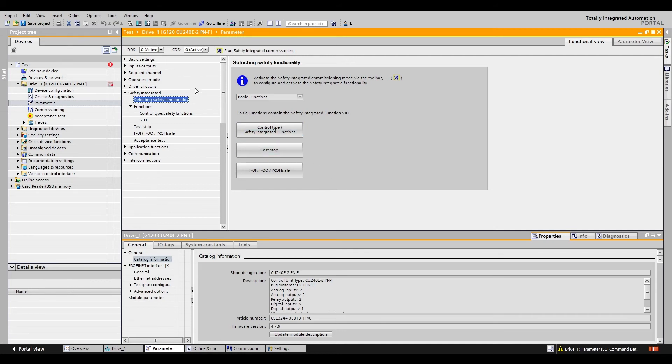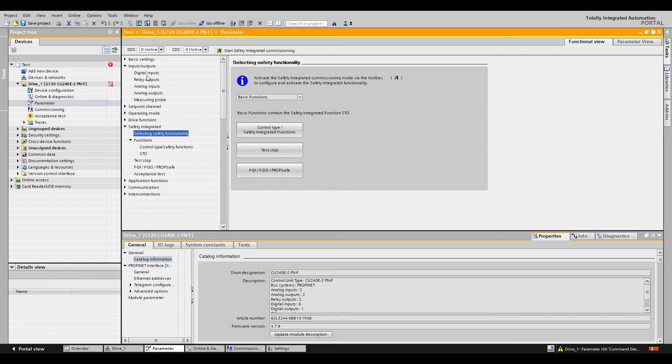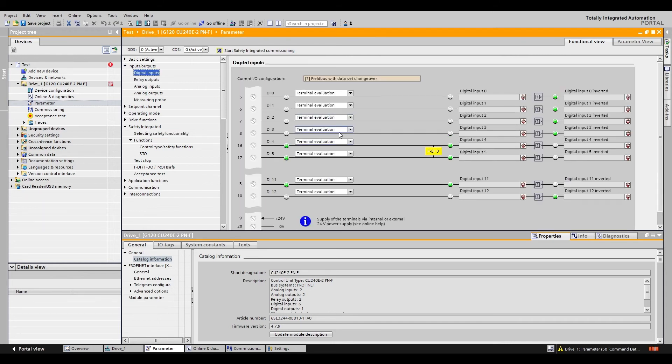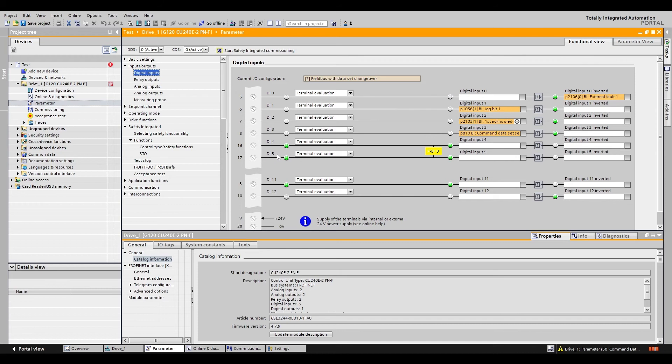Once that's done you can go to your inputs and you can see in your digital inputs that you have your safety circuit on digital input 4 and digital input 5. And these are both high indicating that the safety circuit is active.